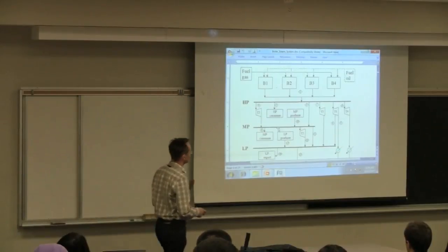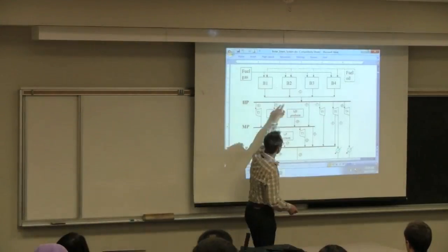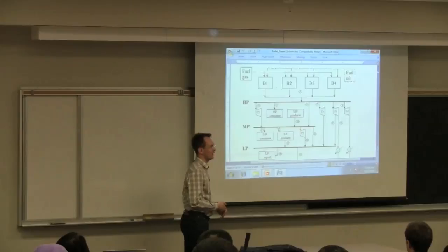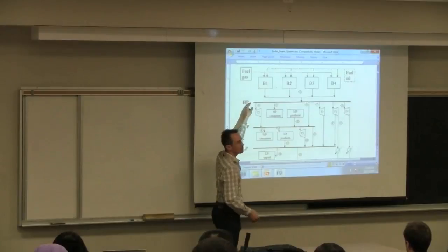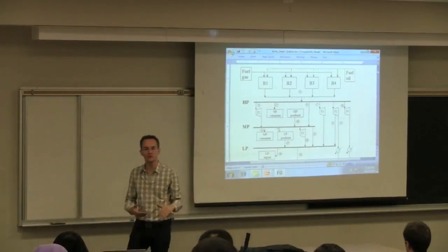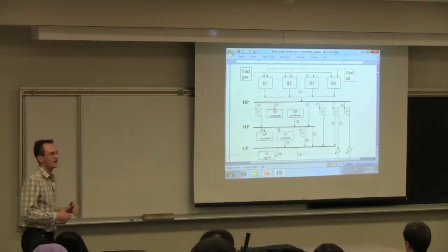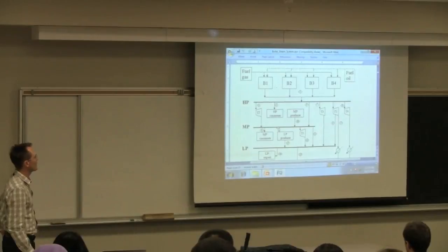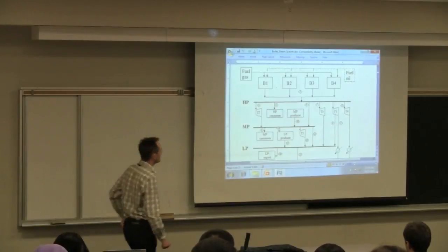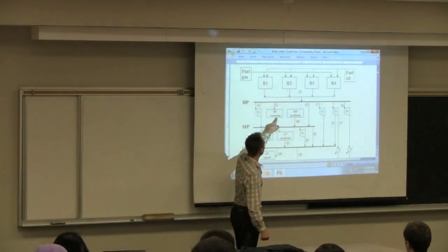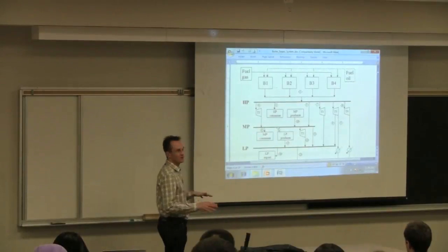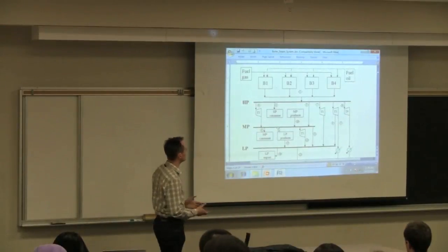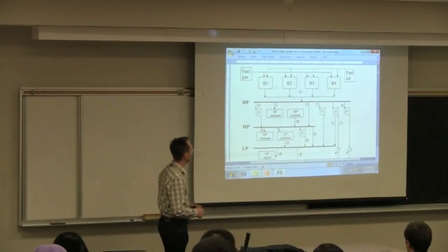Those burners, they all take water, which has been cleaned up of ions and other contaminants, then boil it and provide high-pressure steam. So we create high-pressure steam. We don't create medium and low-pressure steam. The steam is created at a single high pressure. And there may be a number of consumers in the site that require high pressure. So this consumer isn't just one person, it's a number of units in the site that will require high pressure.